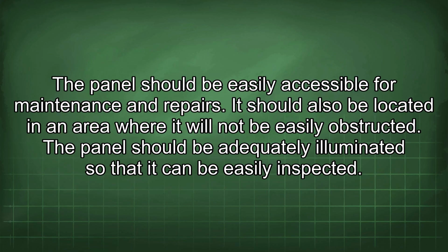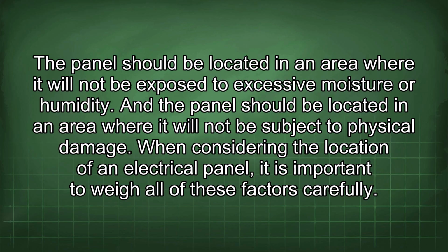The panel should be easily accessible for maintenance and repairs. It should also be located in an area where it will not be easily obstructed. The panel should be adequately illuminated so that it can be easily inspected. The panel should be located in an area where it will not be exposed to excessive moisture or humidity, and the panel should be located in an area where it will not be subject to physical damage.